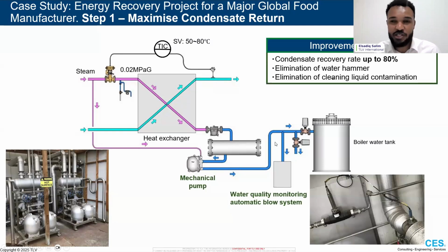But then the second issue is, how do we deal with the risk of contamination? And that's with water quality monitoring. So even applications which have previously been earmarked as impossible to return condensate from, we believe that there's always some negotiation that can be done with site, or some discussion that can be done. And in this case, site installed these turbidity sensors, which will measure essentially the cloudiness of the condensate and measure the impurities of that condensate as it's coming back to the boiler house. If it surpasses a predetermined level that we say we're not happy with, then no problem, it'll dump the condensate, which is what they were doing before.